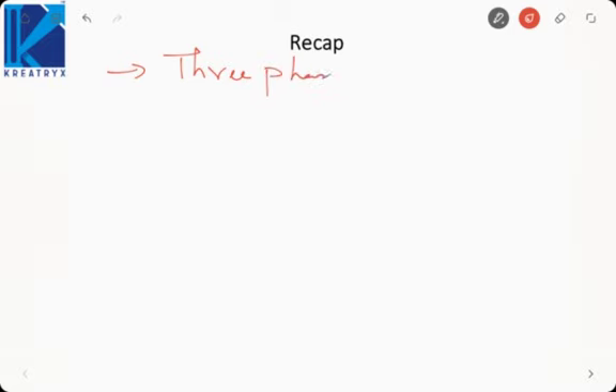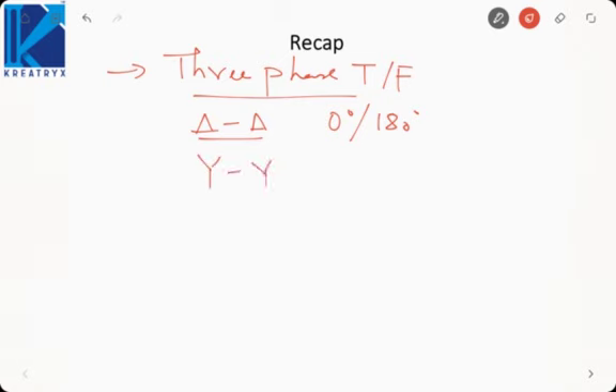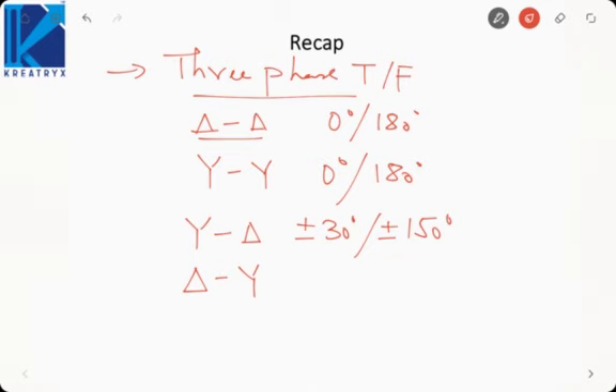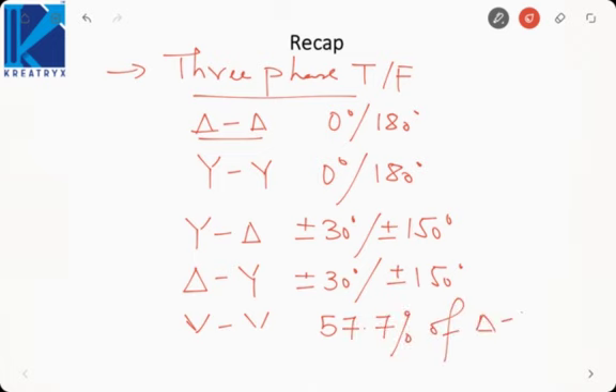We saw various connections of three phase transformer, like we saw delta delta, which had a phase shift of 0 degree or 180 degree, and we saw star star, which also had a phase shift of 0 degree or 180 degree. Then we saw star delta, which had a phase shift of plus minus 30 or plus minus 150 degree, and we saw delta star, which also had a phase shift of plus minus 30 degree or plus minus 150 degree. And we saw open delta or VV connection, which had a capacity of 57.7% of delta delta connection.